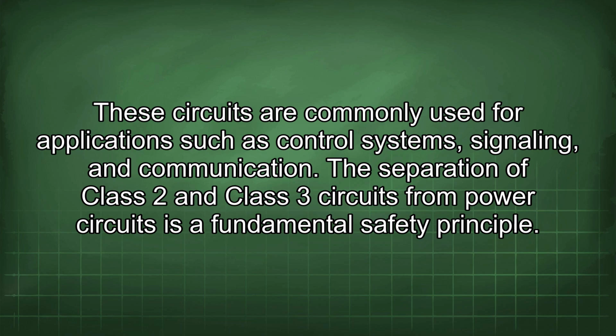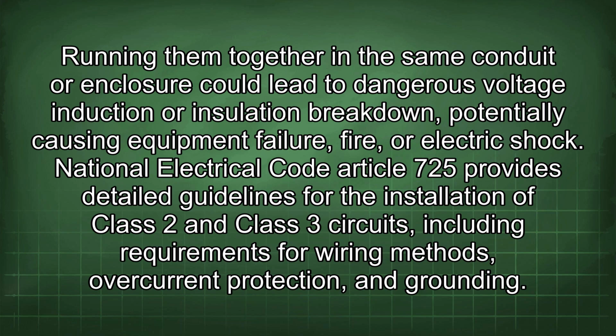These circuits are commonly used for applications such as control systems, signaling, and communication. The separation of Class 2 and Class 3 circuits from power circuits is a fundamental safety principle. Running them together in the same conduit or enclosure could lead to dangerous voltage induction or insulation breakdown, potentially causing equipment failure, fire, or electric shock. National Electrical Code Article 725 provides detailed guidelines for the installation of Class 2 and Class 3 circuits, including requirements for wiring methods, overcurrent protection, and grounding.